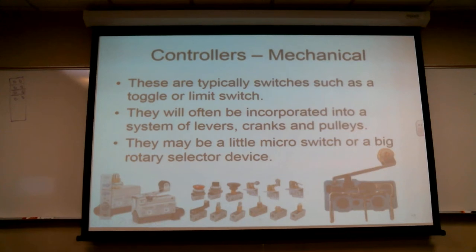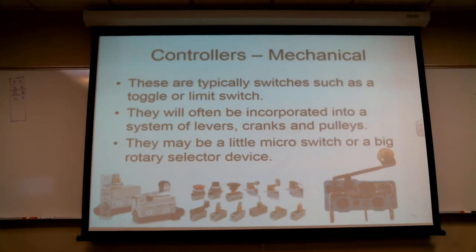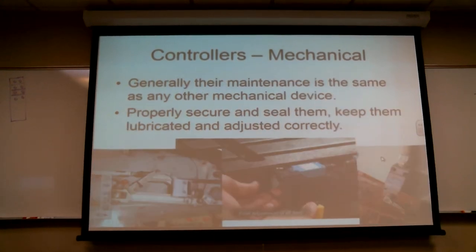Some switches that aren't momentary don't have a normal position — they're either one way or the other, or one of multiples. But a switch with a spring-loaded momentary action, normal is its relaxed state. It's very common for switches to be sold with all three leads, and you can use all three or just two of them. The roller on a limit switch serves a purpose when something moving — like a rotating cam — hits it and rolls along, rather than making a straight point contact.